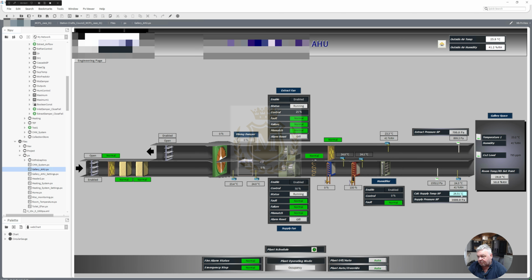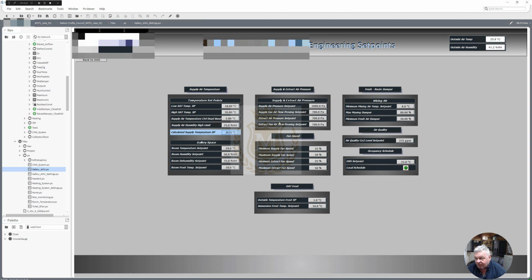Let's just do some simple logic for the free cooling business, because that's what the question was anyway, but it's giving you some ideas of some AHUs, and the logic can be complex. It's not as simple as what you may think, depending on what you need to do. If we look at the engineering page here, we've got the supply and extract pressure, so it can be adjusted. The fan speeds can be adjusted. The gallery space temperature, the temperature set points, from which the calculated supply temperature comes. You've got your mixing air temperatures, your air quality, etc. So let me close this one down and open up a spreadsheet. I'll put you on pause again.